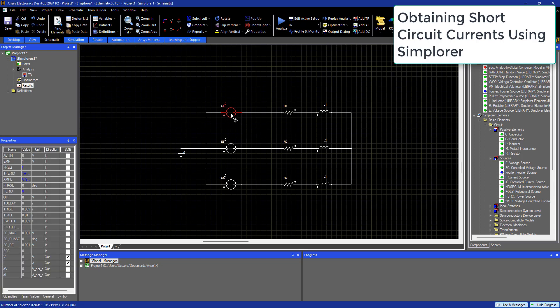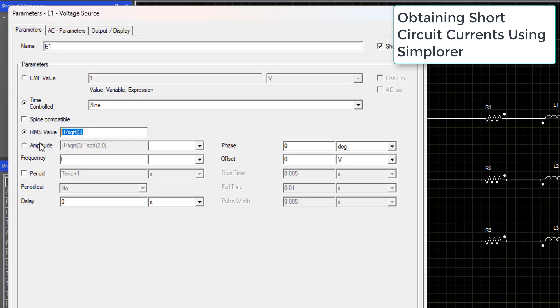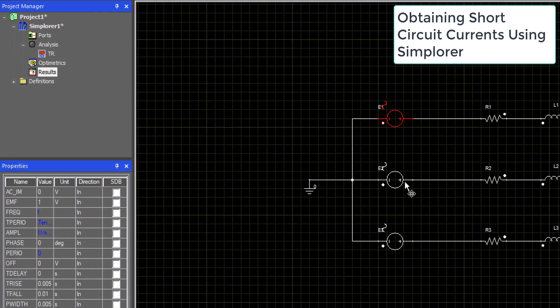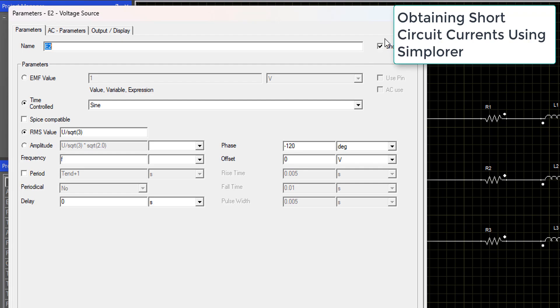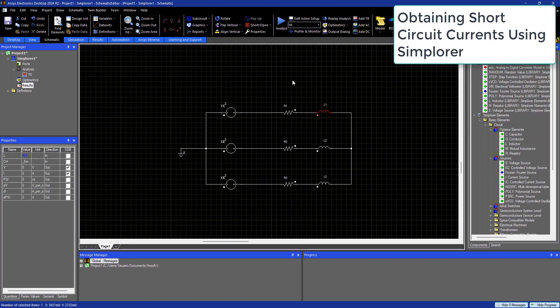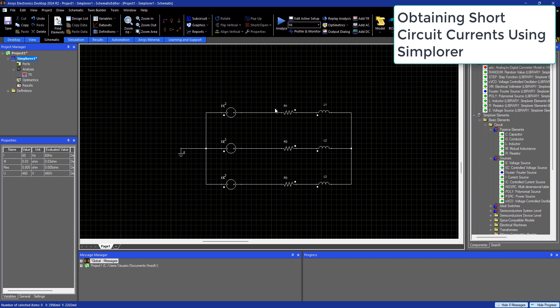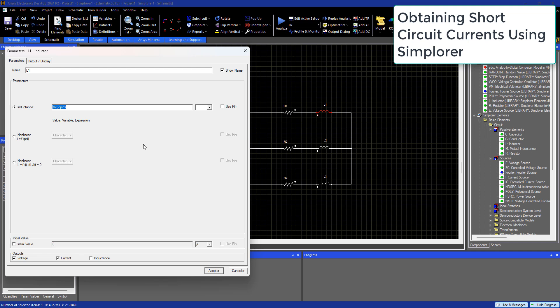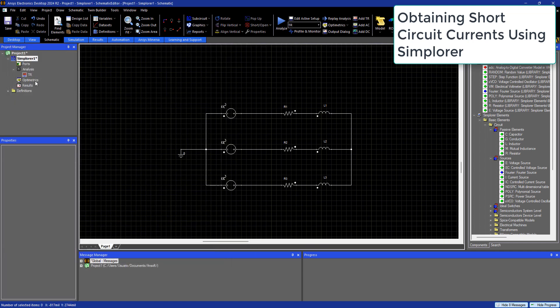We will start our three-phase short circuit analysis using simulation software. We will define three voltage sources in sine wave mode and define their voltages, frequencies, and phase shifts. We will also set the resistances and inductances of the system — this would represent a power transformer in a simplified way — to then perform busbar force analysis.